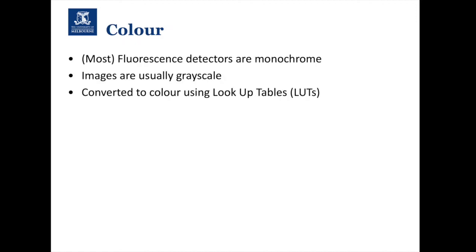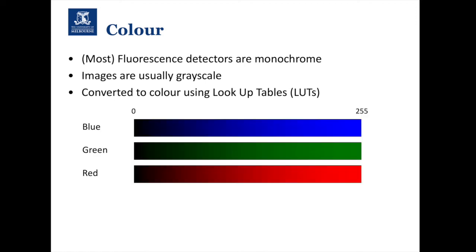First, color: most fluorescence detectors are monochrome, which means your images are usually grayscale. Any color we're seeing is being converted from grayscale into color using something called a lookup table. Three of the most commonly used lookup tables are the blue, green, and red lookup tables. In each case, zero intensity is black, maximum intensity is the chosen color — blue, green, or red — with a linear scale in between.